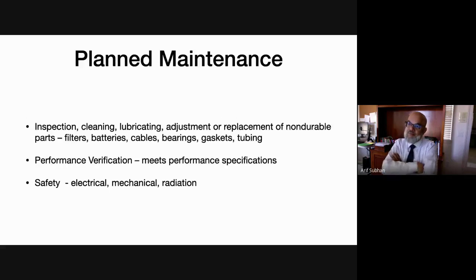Okay. Planned maintenance. I mean, biomed technicians do spend a lot of time every day in the hospital doing maintenance on the different types of devices that are there. And when we're talking about planned maintenance, we're talking about inspecting devices, cleaning devices, lubricating, adjusting, replacing sometimes non-durable parts, which includes filters, batteries, cables, bearings, gaskets, tubing, you name it, anything that's called for in the service manual.